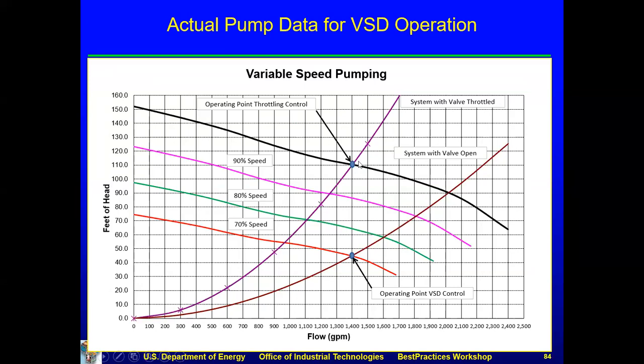So the assumption is when you open the valve 100%, your system curve is going to relax because it has less resistance, and you're going to come out here and you would operate at your regular full speed pump curve. You would operate here, which is about 2,000 GPM at, looks like about 90 feet of head. But when we go in and examine the system, you go, oh, look at this valve. It is pinch, pinch, pinch. I measure 1,400 GPM, and the pump head is 110 feet.